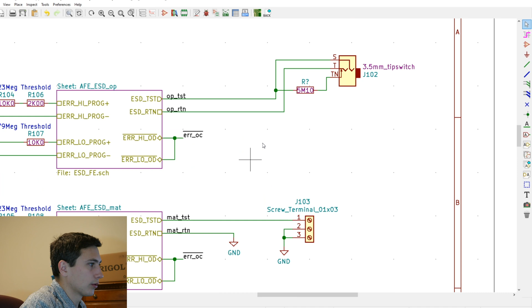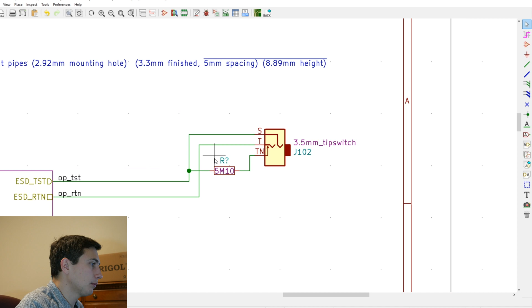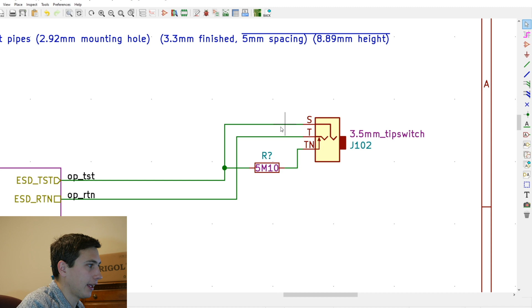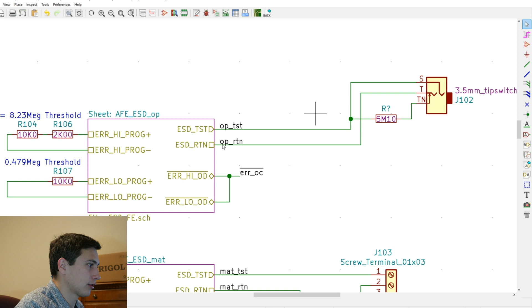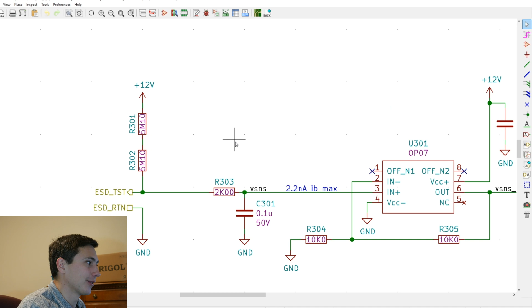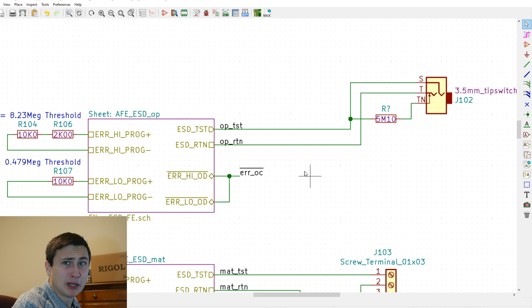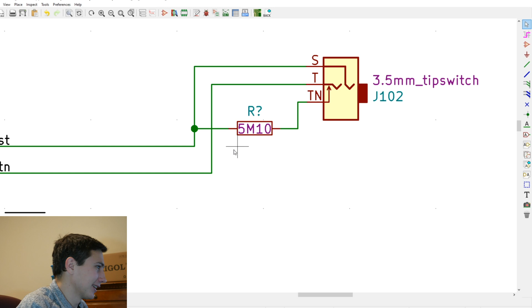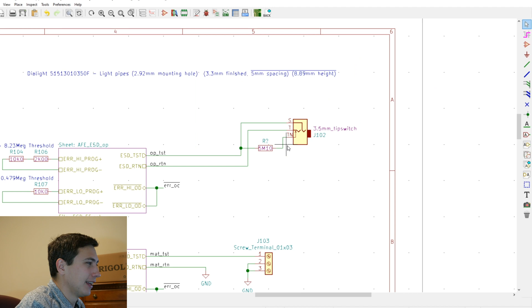And then on the other side, for the operator, we're using the tip switch to connect between the tip and the return. So basically, when you don't plug in your operator ESD strap, the switch itself will connect a 5 meg impedance across it, which should cause it to not beep at you. So if you unplug it, it'll stop monitoring, which is awesome, because I might want to unplug it sometimes—that's a real use case if we just want the bench and not the operator strap. This gives us a quick way to disable that.